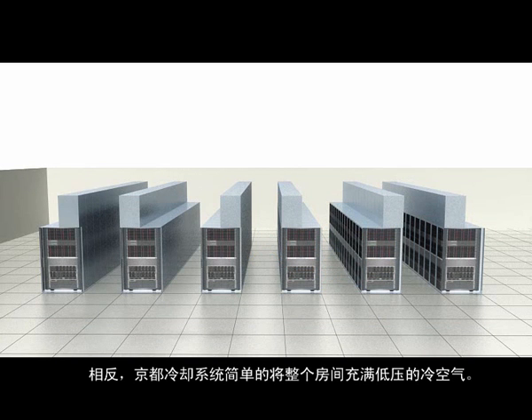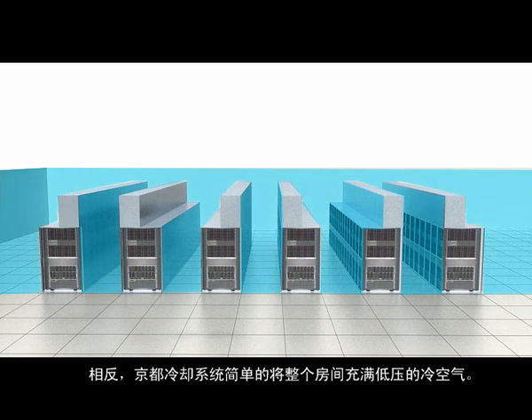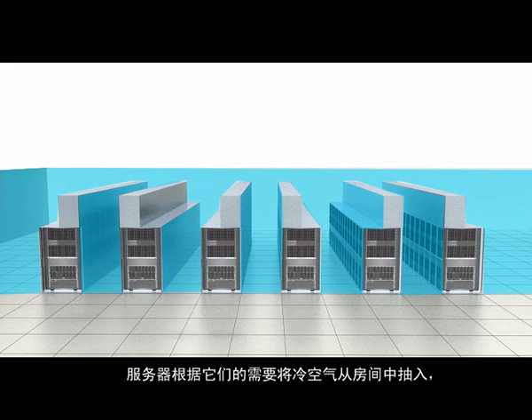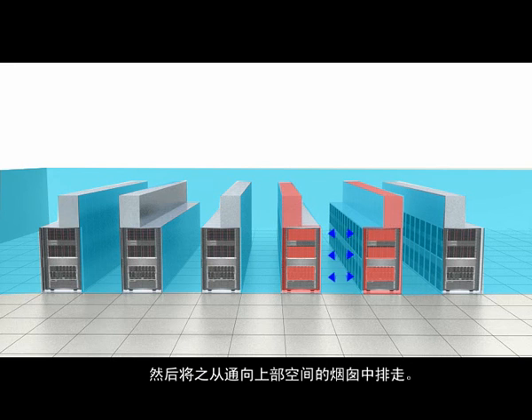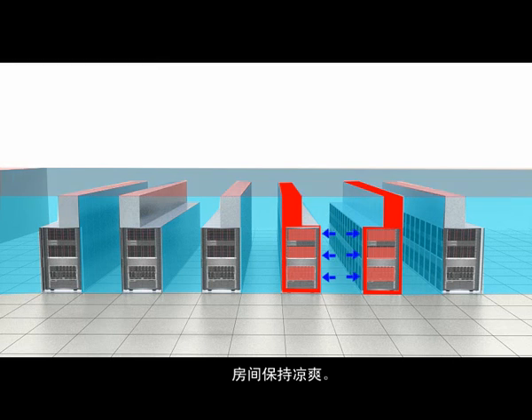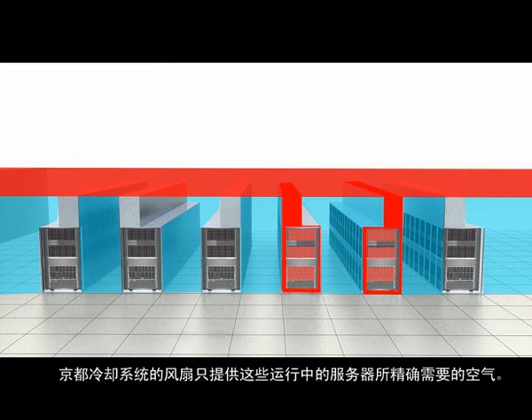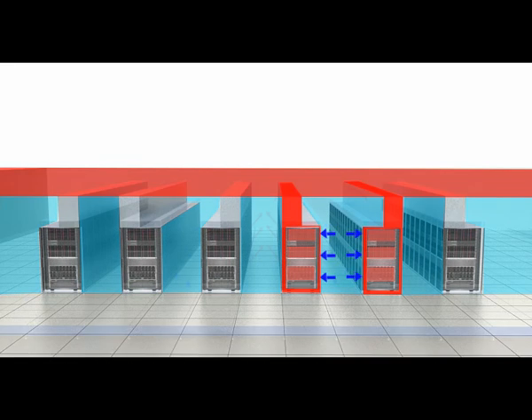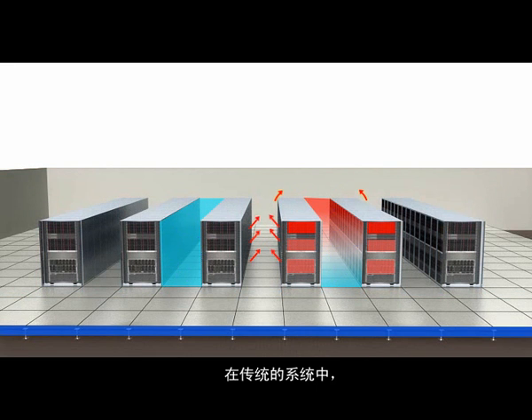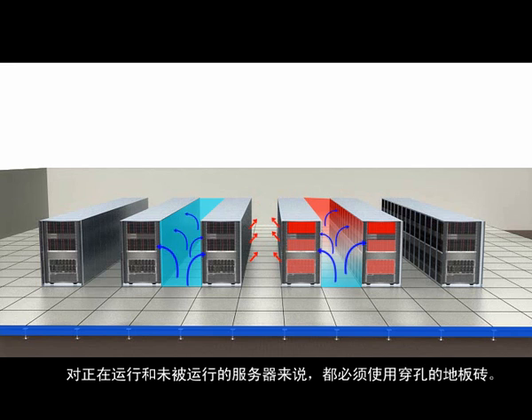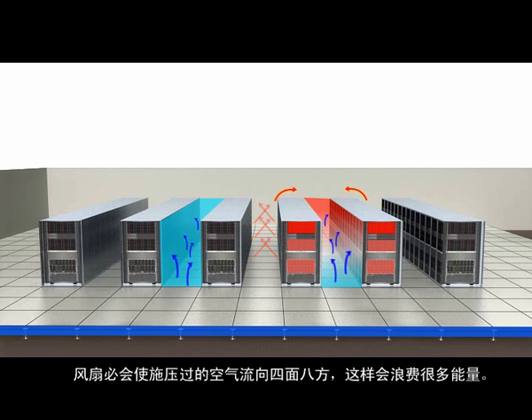KyotoCooling, on the other hand, simply fills the room with cool air at low pressure. The servers draw the cool air they need from the room and discharge it through chimneys to the return air plenum above. The room stays cool. KyotoCooling provides the precise amount of air required by the active servers. In traditional systems, perforated tile must be installed for both active and inactive servers. Fans must move pressurized air to all locations, wasting energy.